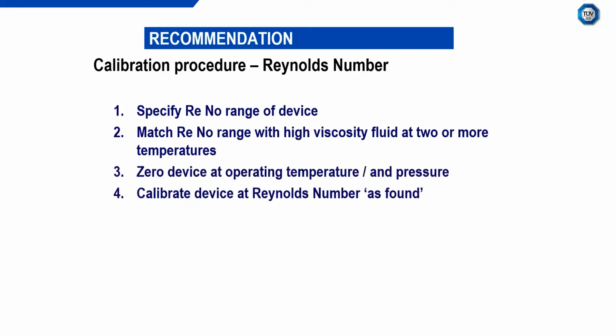We then zero the device at operating temperature and pressure. We calibrate the device at the Reynolds number as found. We decide if the Reynolds number effect is significant. Now I must stress this. I said before that for pressure, all meters were affected. What we're finding for Reynolds number is that not all meters are affected.